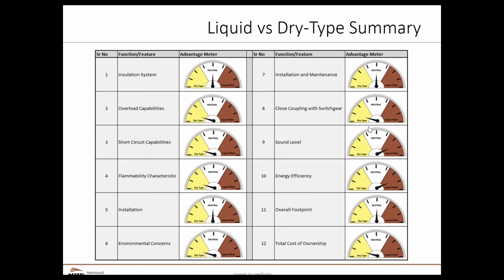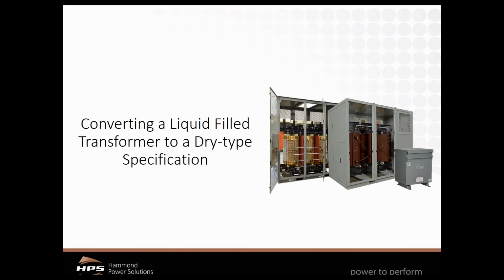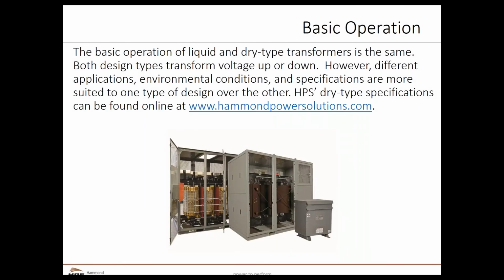technologies. The next presentation that I'm going to move to is when we talk about converting a liquid-filled transformer to a dry type specification. What has to be done in order for us to accomplish that? And again, what we're trying to say is that the basic operation of liquid and dry type transformers is the same. A lot of times we're changing voltage, we're providing possibly some harmonic mitigation depending on how the phases are arranged. We might obviously be providing short circuit mitigation, stuff like that.